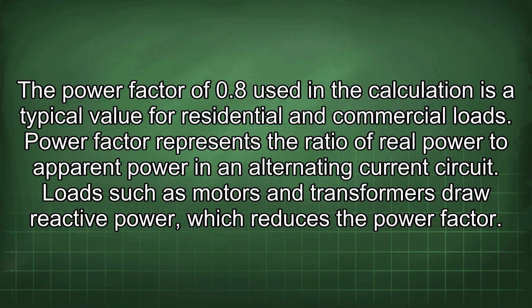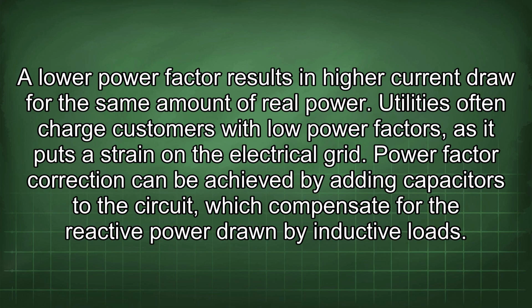Power factor represents the ratio of real power to apparent power in an alternating current circuit. Loads such as motors and transformers draw reactive power, which reduces the power factor. A lower power factor results in higher current draw for the same amount of real power. Utilities often charge customers with low power factors, as it puts a strain on the electrical grid.